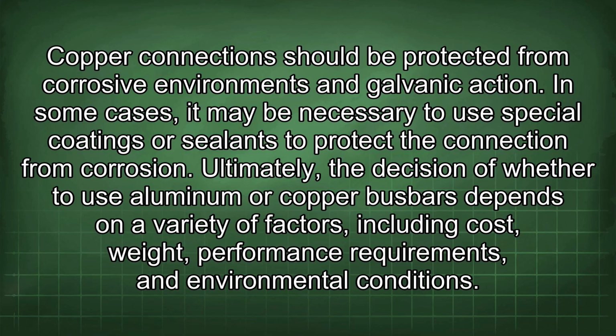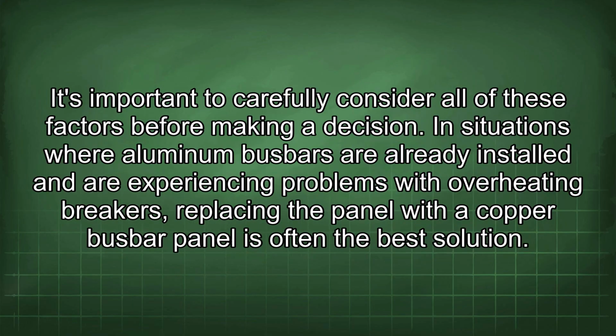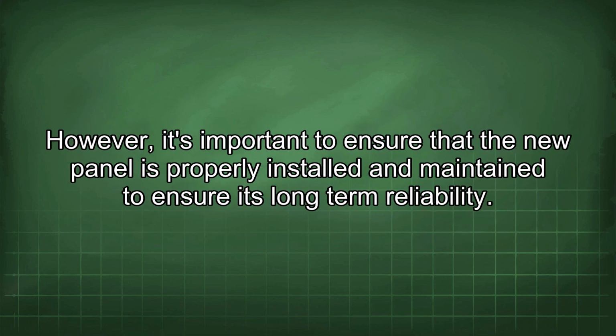Ultimately, the decision of whether to use aluminum or copper busbars depends on a variety of factors, including cost, weight, performance requirements, and environmental conditions. It's important to carefully consider all of these factors before making a decision. In situations where aluminum busbars are already installed and are experiencing problems with overheating breakers, replacing the panel with a copper busbar panel is often the best solution. However, it's important to ensure that the new panel is properly installed and maintained to ensure its long-term reliability.